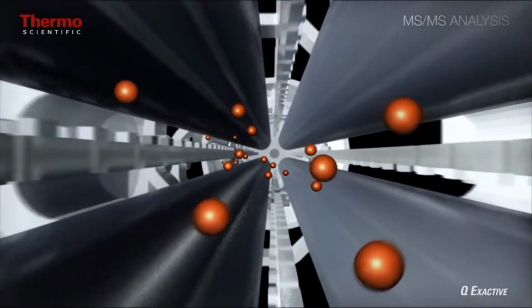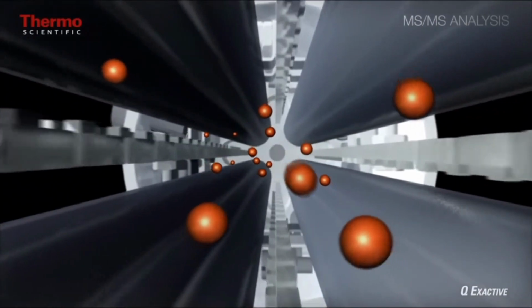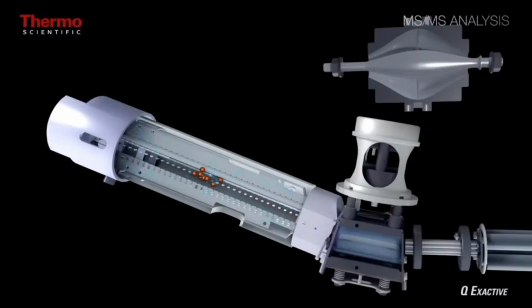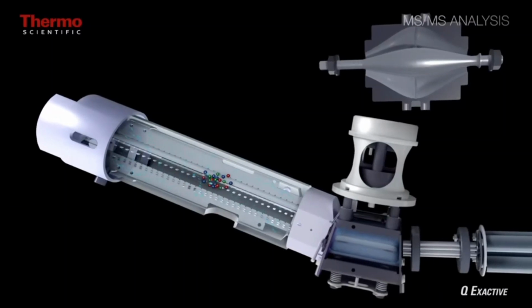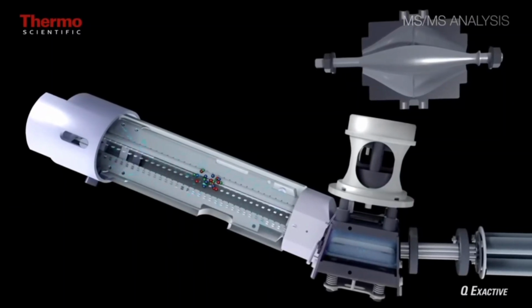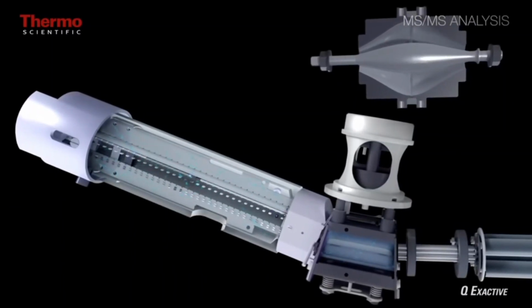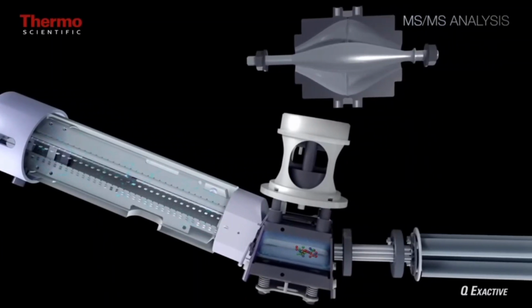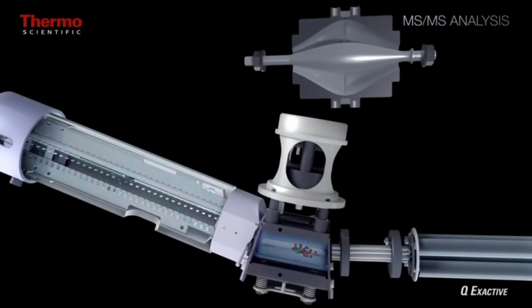It's going to enter the collision chamber. And in the collision cell, you have a determination to make about what your fragmentation energy is going to be. Are you going to bias this more for fragmenting your reporter ion? Do you want to get more diverse fragments from your precursor species? Considerations that one has to make. Collection time, again, for the fragments is another consideration.